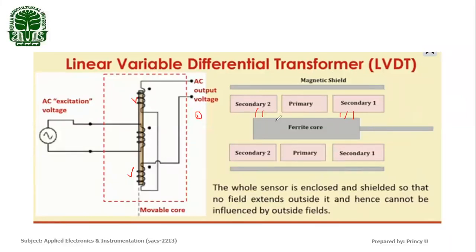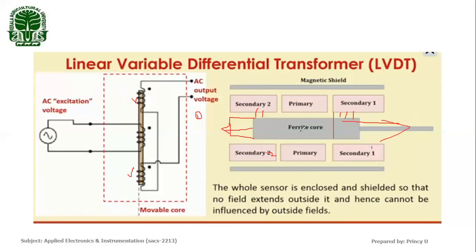When we move the ferrite core in one direction, the core reaches the region of the first secondary coil and detaches from the second. The voltage induced in the first secondary increases while the voltage induced in the second secondary decreases. So there is a difference in voltage and an output voltage is produced. When we move the core to the other side, there is no induced EMF in the second secondary coil, but there is an output voltage in the first secondary. The output is the difference of these two voltages.